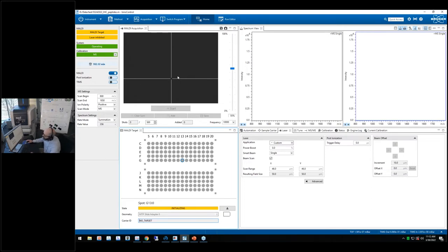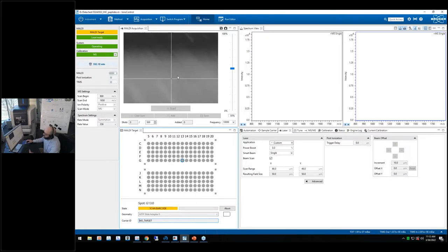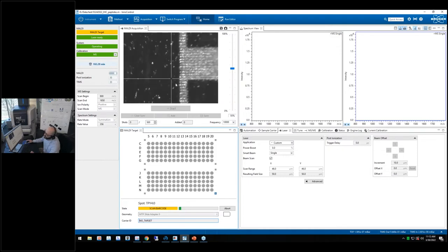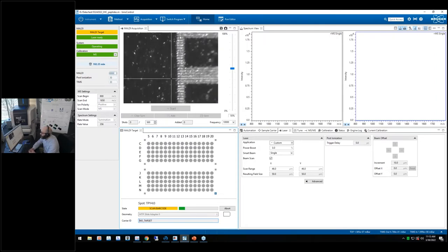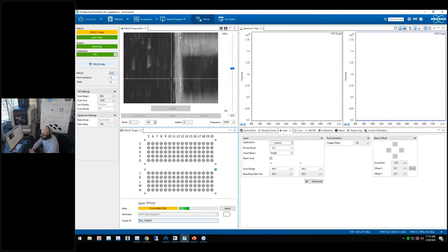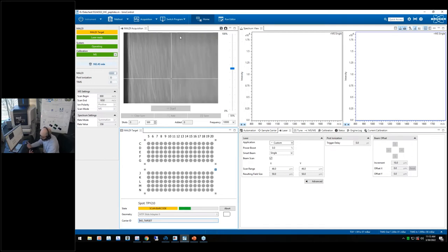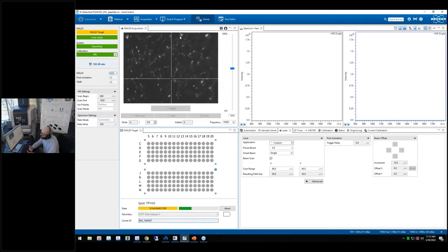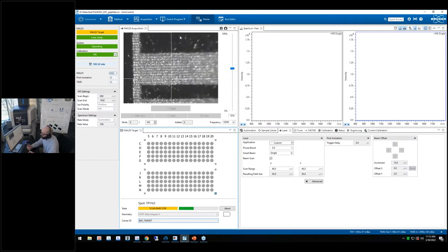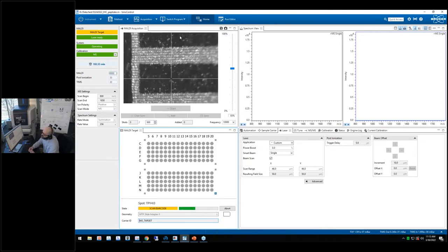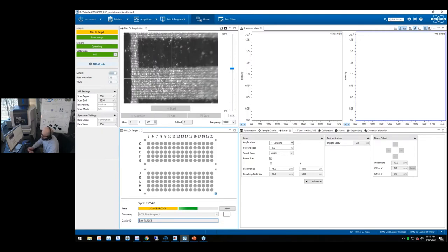One of the neat features of the instrument is that the IntelliSlides and the MALDI targets we use have barcodes and other marks on them. So right now we can see the camera is actually scanning over a barcode. The IntelliSlides barcode will actually be automatically registered to a database on the instrument PC, and this will help facilitate high throughput measurements and keeping everything nice and in order. You won't be able to overwrite data and things like that. So it's a really nice, useful feature.